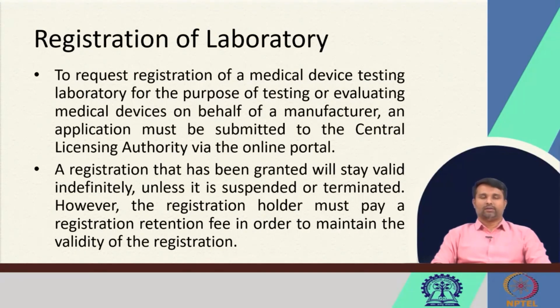Registration of laboratory. Before the approval, the medical device has to be tested in a recognized laboratory. To request registration of a medical device testing laboratory for the purpose of testing or evaluating medical devices on behalf of a manufacturer, an application shall be submitted to the central licensing authority via the online portal. Once granted, the registration is valid indefinitely unless it is suspended or terminated. However, the registrant must pay a registration retention fee in order to maintain the validity of the registration.